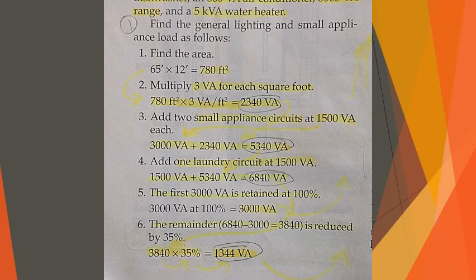Step 5, the first 3,000 VAs is retained at 100%, and the remainder is reduced by 35%. So we take 3,000 from 6,840. We are left with 3,840. We have to reduce that by 35%. We multiply it by 0.35, so 3,840 times 0.35 gives us 1,344 VAs. Of course, we have to add that to the 3,000 VAs which we have at 100%. We get 4,344 VAs. This again is the net lighting and small appliance requirement, 4,344 VAs.